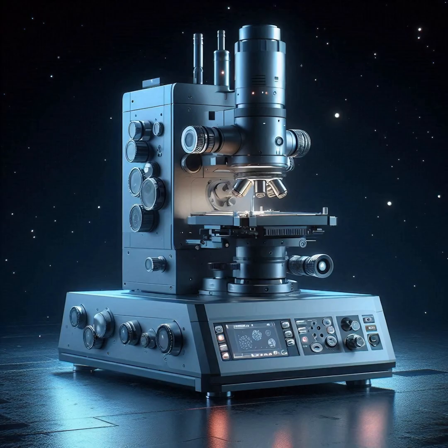For example, the image may be viewed directly by an operator using a fluorescent viewing screen coated with a phosphor or scintillator material such as zinc sulfide. More commonly, a high-resolution phosphor is coupled by means of a lens optical system or a fiber optic light guide to the sensor of a digital camera.